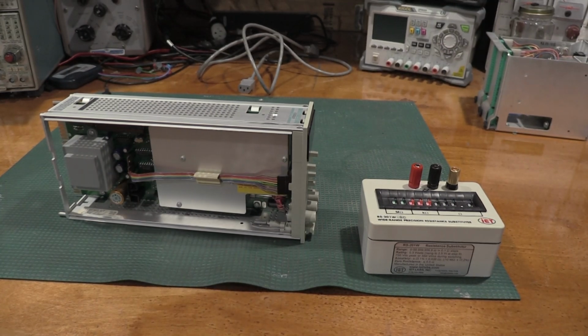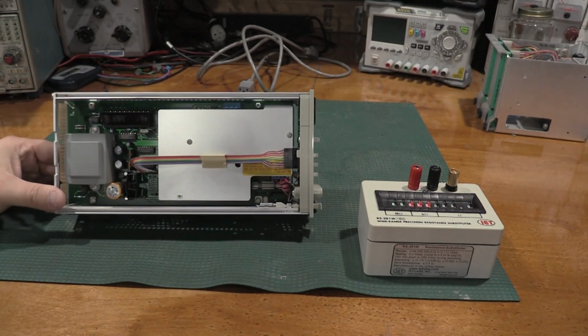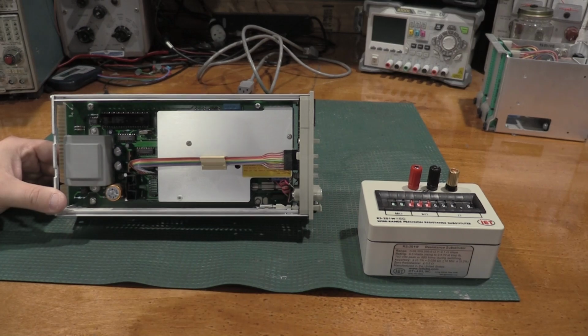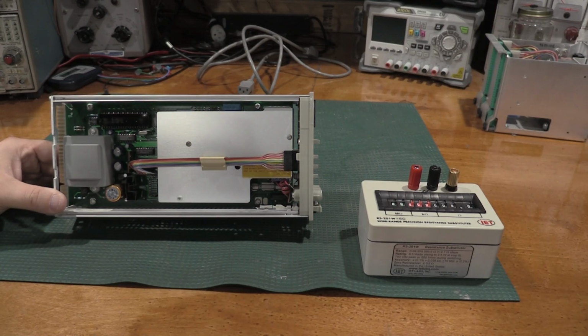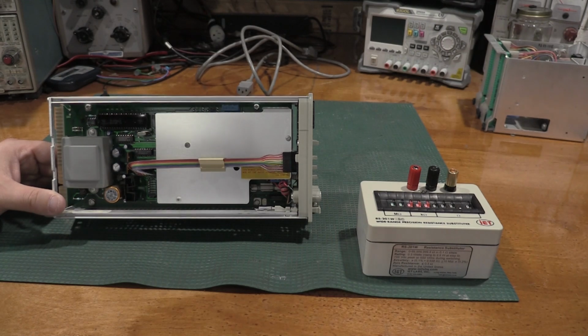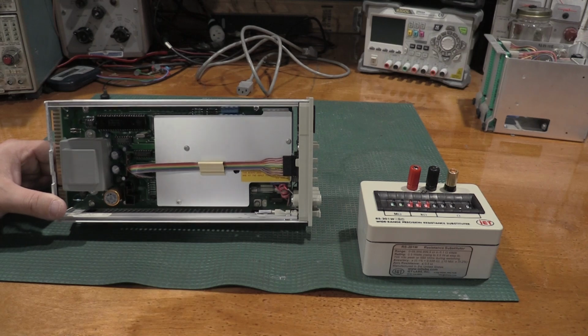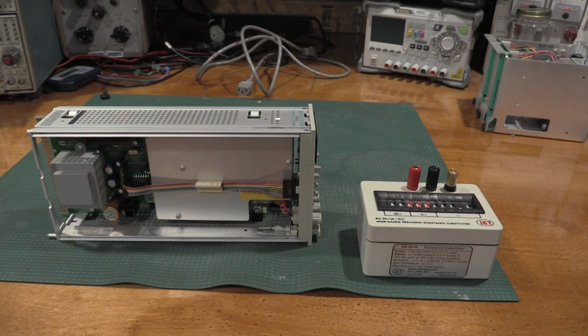So the rebuild on this meter is actually pretty straightforward. Got a couple capacitors that the owner would like replaced, and that's about it. So the rebuild's going to take me like 10 minutes, 15 minutes. The alignment is going to take me a while, because you have to do every single range. And on the DC side, you actually have to do every single range, positive and negative.